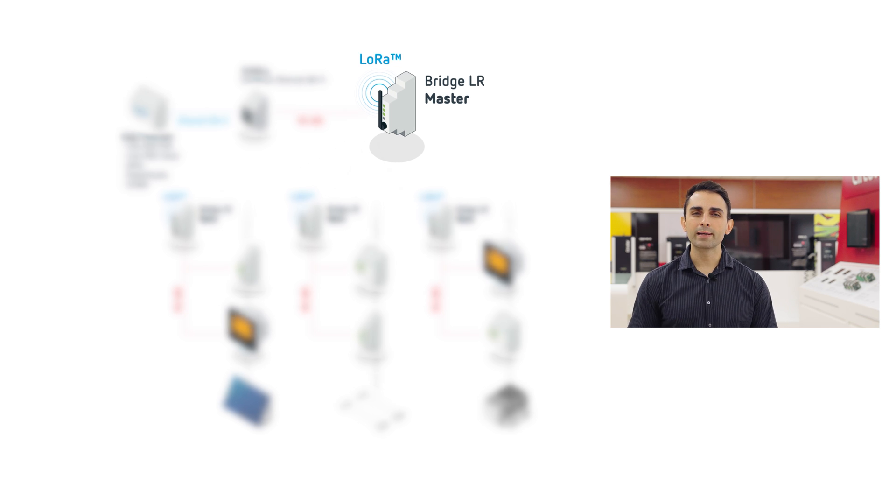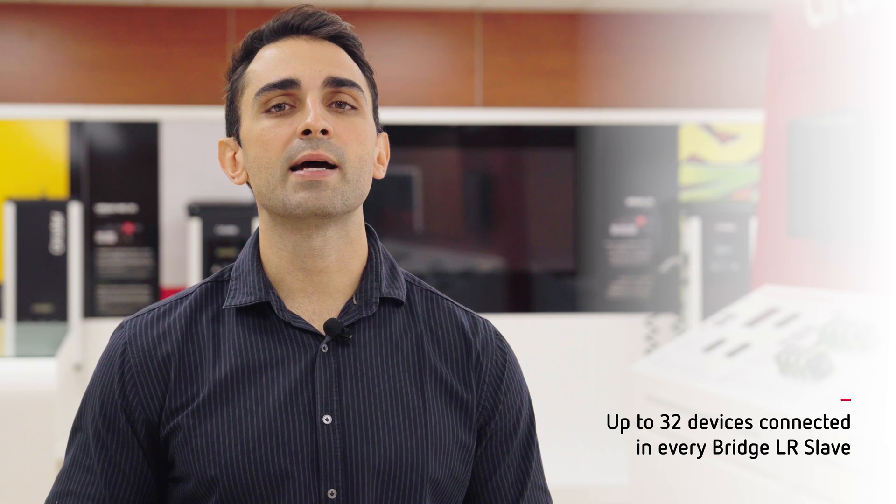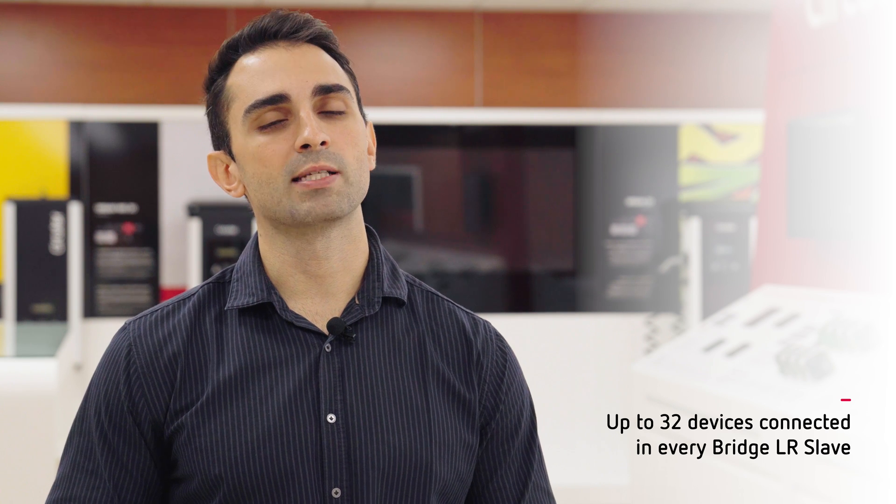To integrate the LoRa solution, a Bridge LR configured as a LoRa master must be installed directly wired to our Modbus master, and as many Bridge LR slaves as locations or sub-panels with measurement devices. Behind each Bridge LR slave, you can connect up to 32 devices on each RS-485 bus.